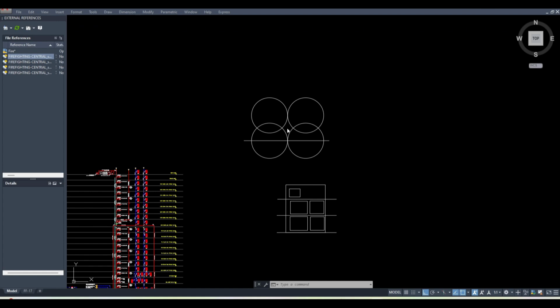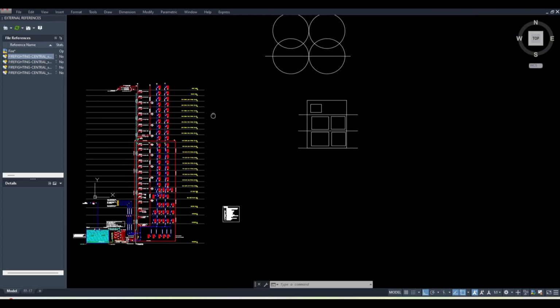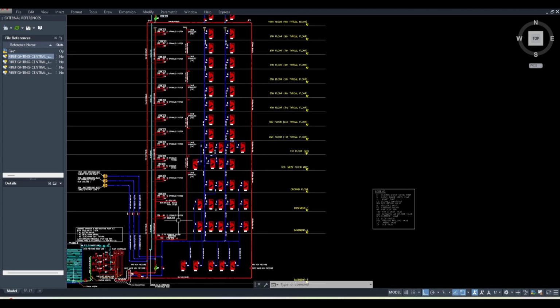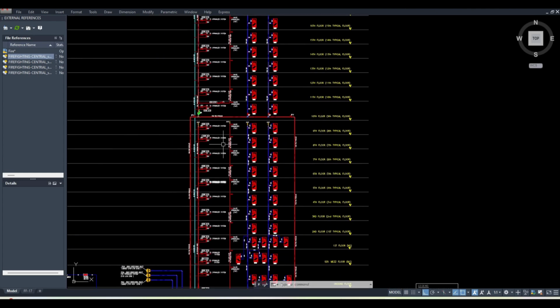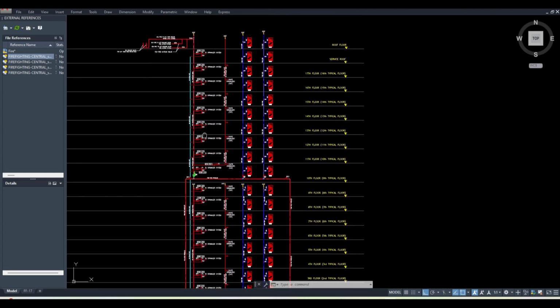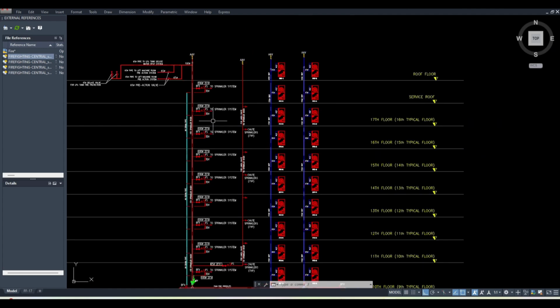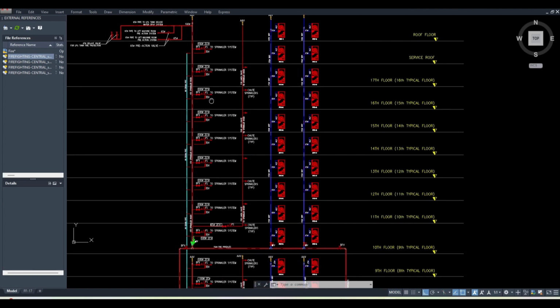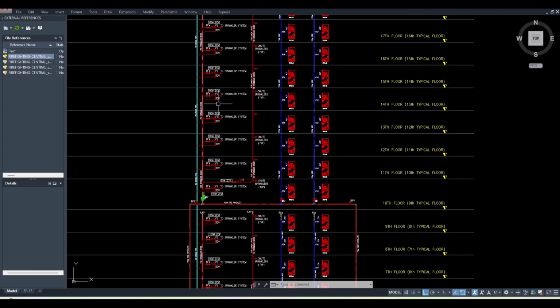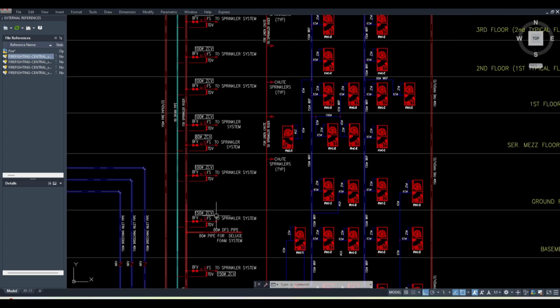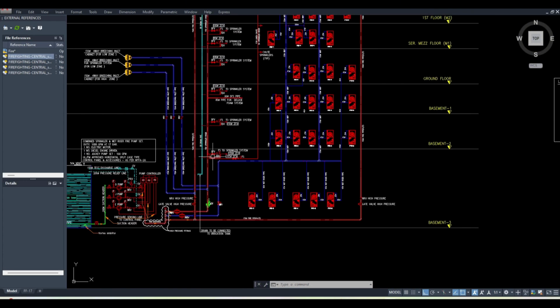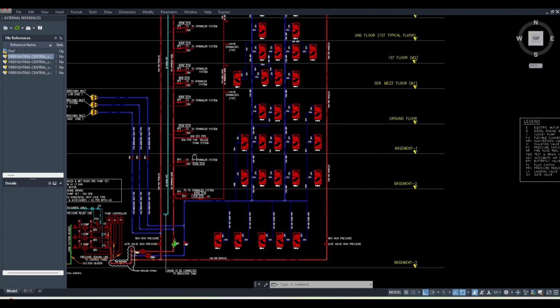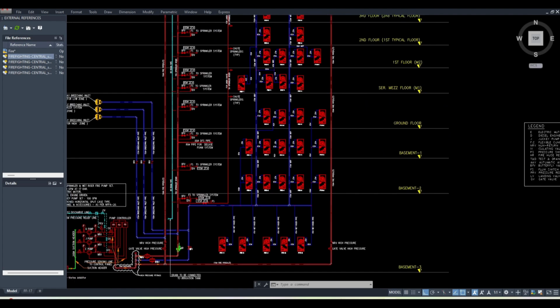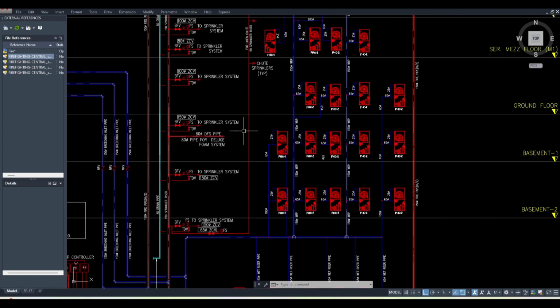Okay, now I'll go to the principle of how it works. Basically, if a fire is happening, and now these calculations, once again, how they calculate it: one fire at one place. So here you can see that these zone control valves are meant not to operate at the same time, but if a fire is happening, then in that case the sprinkler will break.